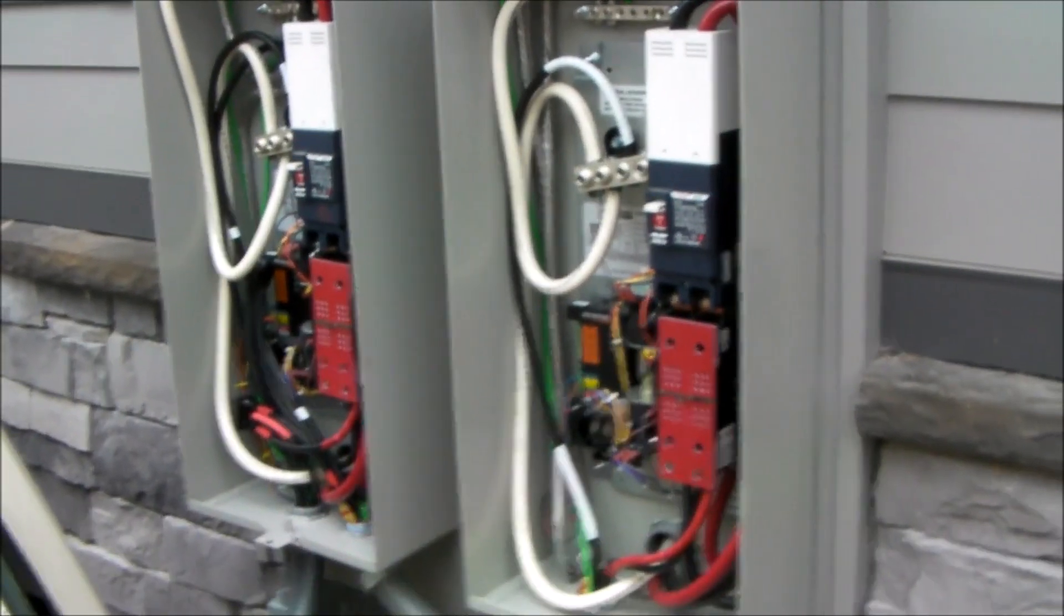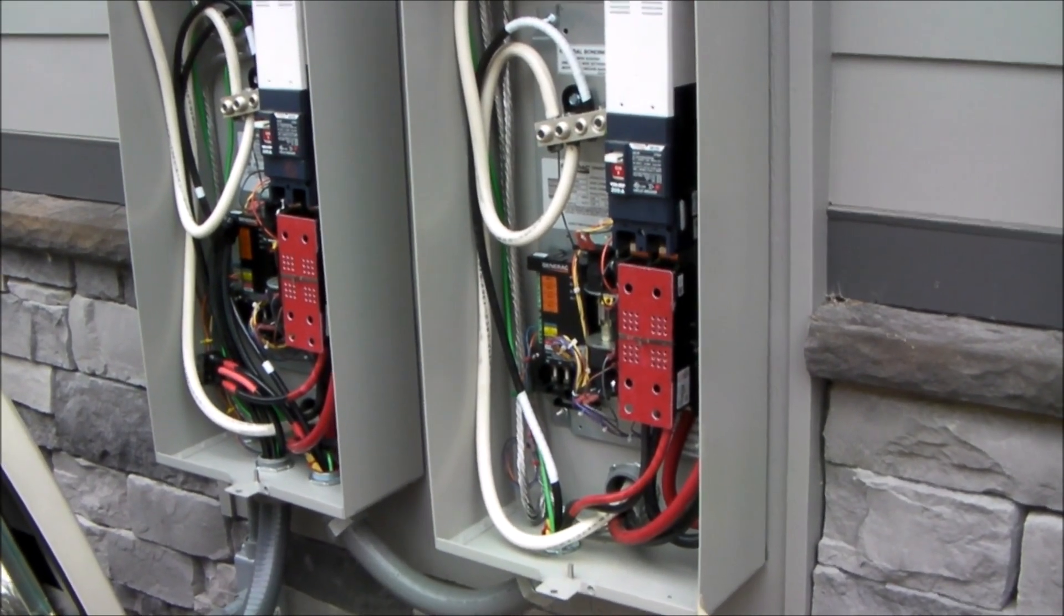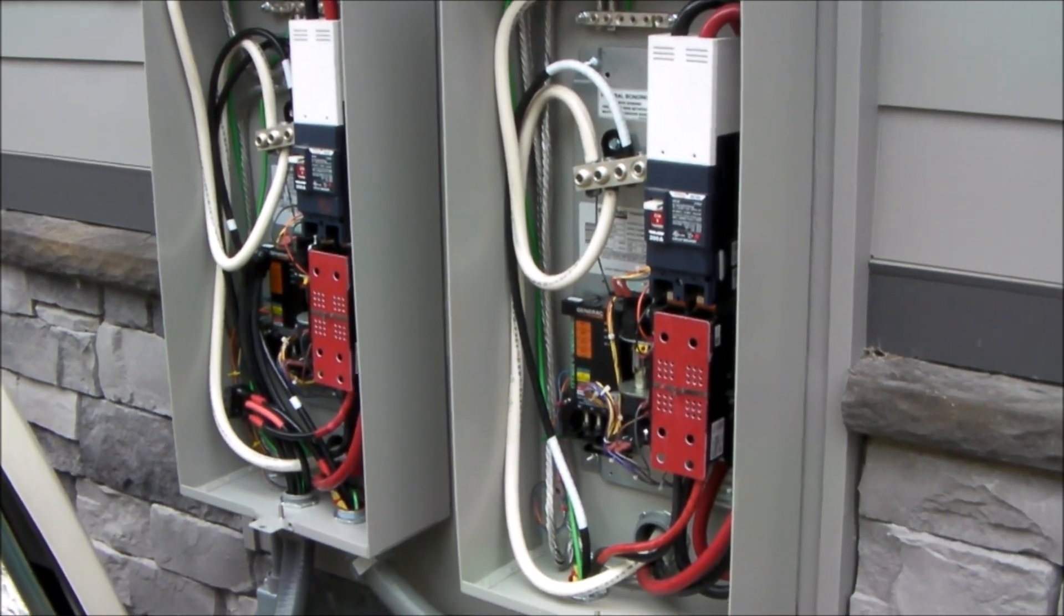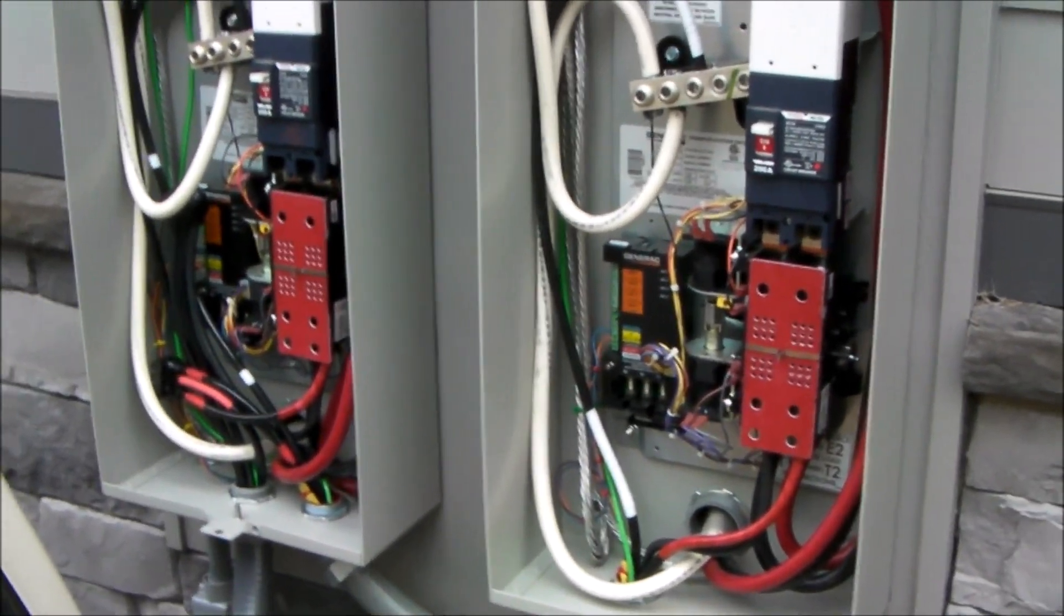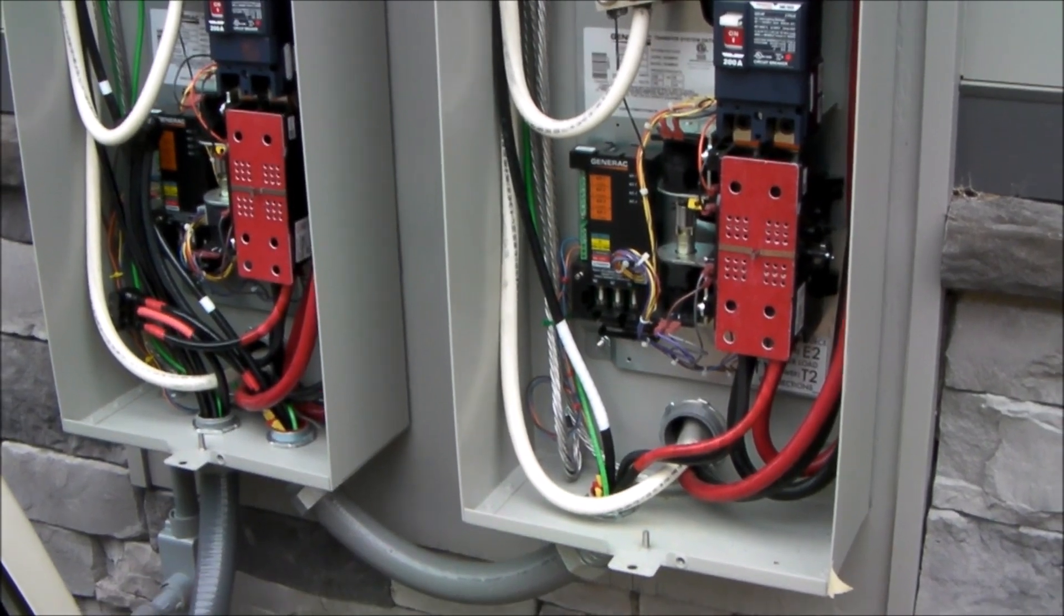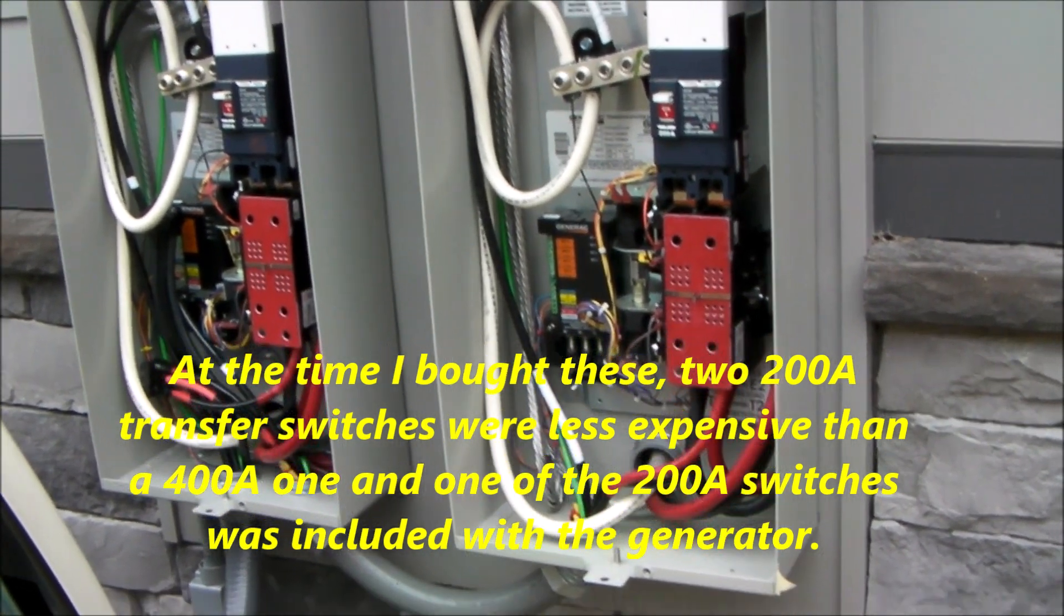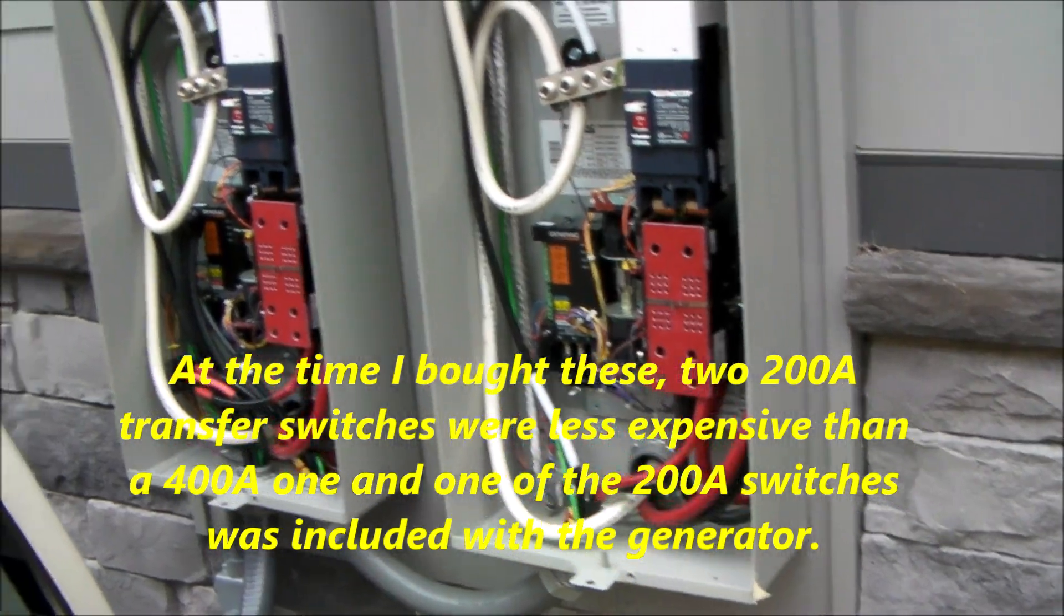I went with two 200-amp transfer switches for one reason. I have 400-amp service coming into the house. I have two 200-amp load centers in the house, so each one of these transfer switches powers one of the load centers. Additionally, I think a 200-amp transfer switch is a lot easier to get and generally less expensive than a 400-amp transfer switch. You have a little bit of wiring to deal with, but not all that bad at the end of the day. I'm going to button it all up, and we're all set and ready to go.